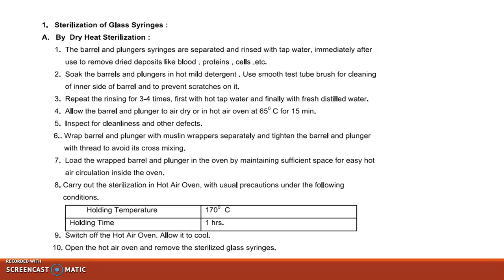Then repeat the rinsing 3 to 4 times, first with hot tap water and finally with fresh distilled water. Now allow the barrel and plunger to air dry in the hot air oven at 65 degrees Celsius for 15 minutes. Inspect the cleanliness and other defects. Now wrap the barrel and plunger with muslin wrappers separately and tie the barrel and plunger with a thread to avoid cross mixing.